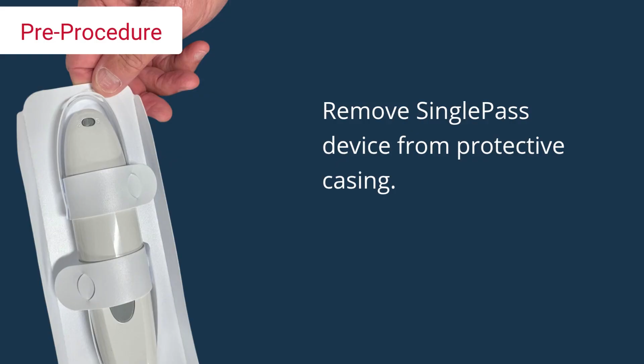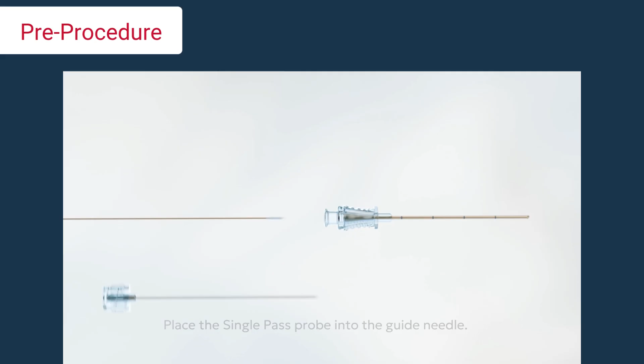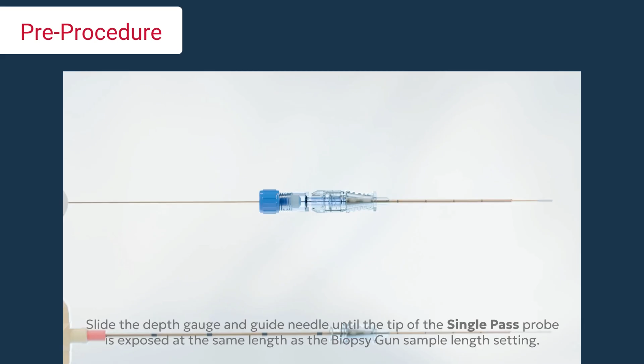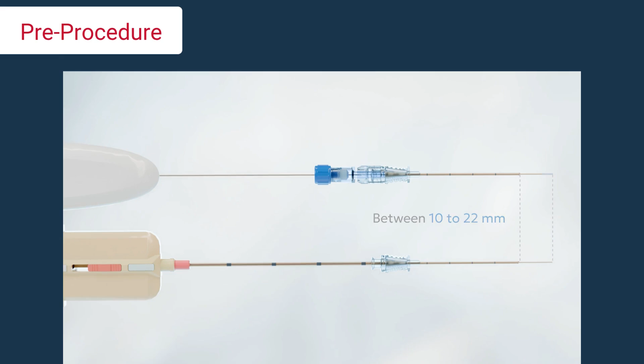Take the SinglePass device out of the protective casing, taking care to gently remove the cautery needle. Remove the sharp stylet from the guide needle and place it to the side. Insert the SinglePass probe into the guide needle and connect the guide needle to the depth gauge. Adjust the probe until the probe is exposed at the same length as the biopsy sample length setting, typically 10 to 22 millimeters. You can use a sterile ruler to measure the distance if desired.